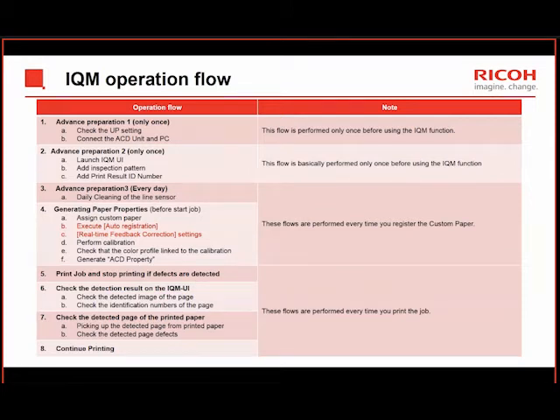So train your customers. You have to train them on the user interface. You have to train them that the message they get on the operation panel, just because it says you've got an error code, it's an error code that relates to the image, not an error code that relates to the machine. So you have to look at the user interface. You have some self-maintenance that the customer can do. You have to go through all of this with them in order to make this system work as it should. And if you don't go through this training with your customer, well, then you will just have more work to do, because you will be called out. And that's what we don't want to happen.